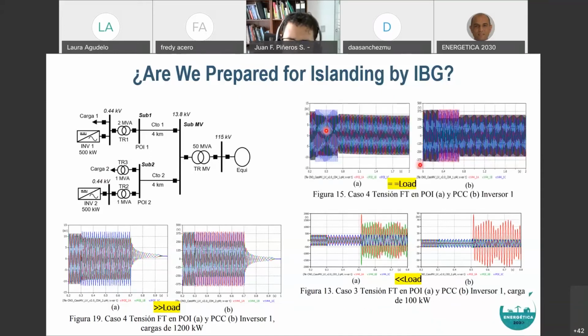But what will happen when you have a balance between the load and the inverter-based generation, and you trip the main transformer that connects this network to the power system? You can have a balance. Of course, this balance can be kept depending on the PLL technology of the inverters. As we know, normally many inverters have a poor PLL system that is not able to keep tracking the system as a result of the opening of this transformer. Then probably there will be a disconnection after some oscillation of the voltage. But if you have a good tracking system with the PLL, the balance could stay there, and you have to handle this, so that you don't have any problem or low voltage condition.